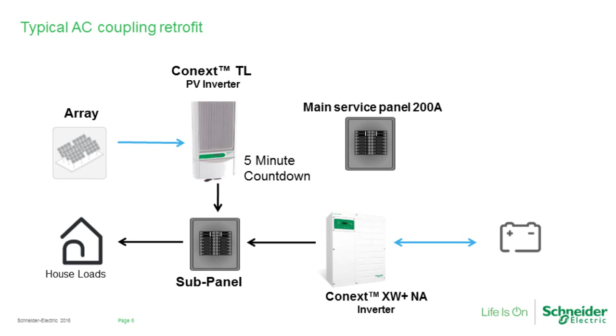But in short, when we're consuming power on the sub panel, any extra power produced by the PV inverter is going to go onto the batteries. And at some point, those batteries are going to get full and we'll need to disconnect. But again, we'll touch on that a little bit later. The nice thing with this system is, of course, those house loads are going to remain backed up permanently until either the batteries run out of power or the grid comes back, because the PV inverter is going to provide power first to the house loads. But then when the sun goes down, the Conext XW+ is going to be the primary source for AC power to those house loads, because it is that grid forming inverter.